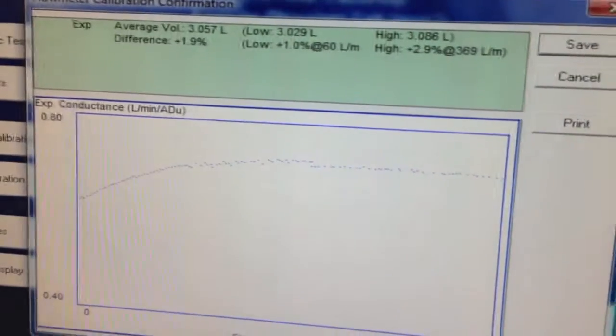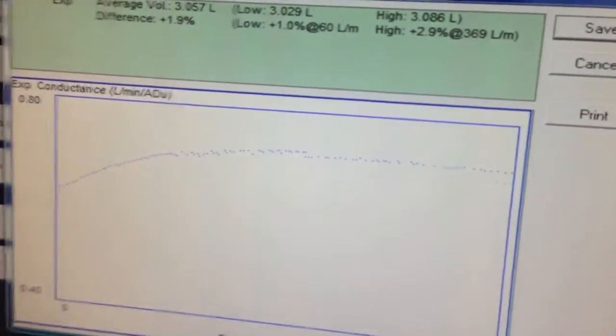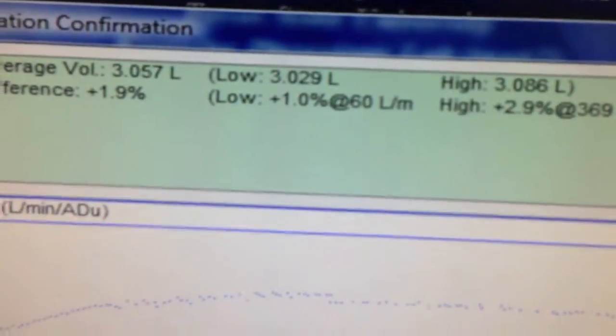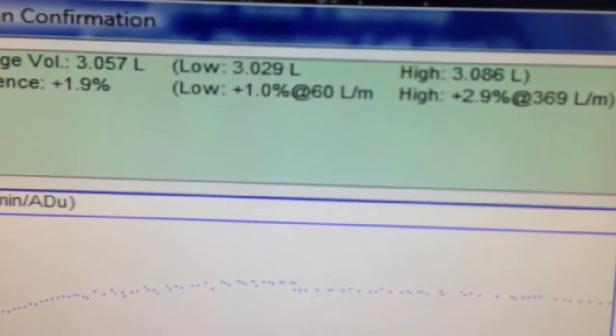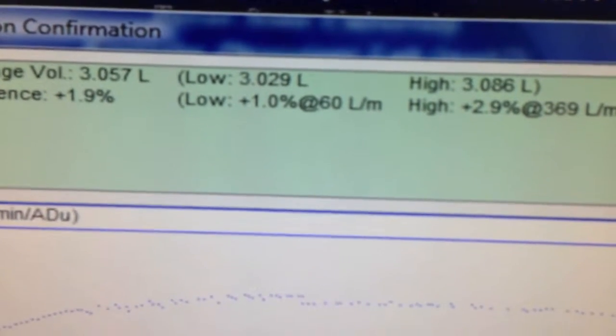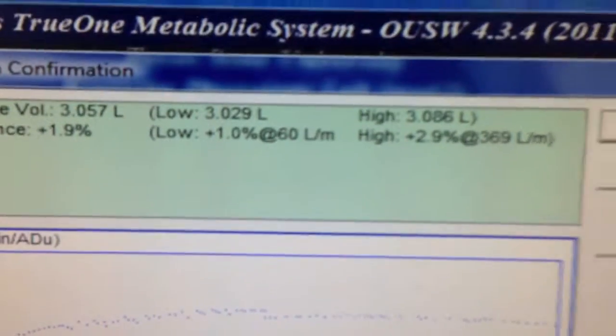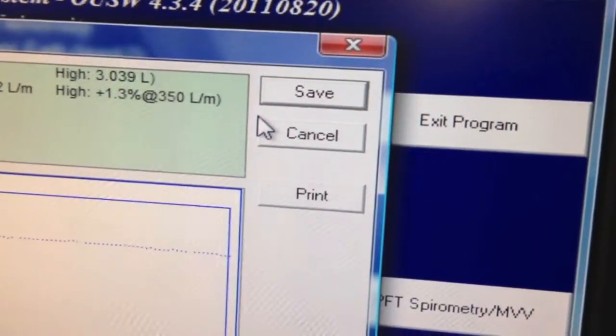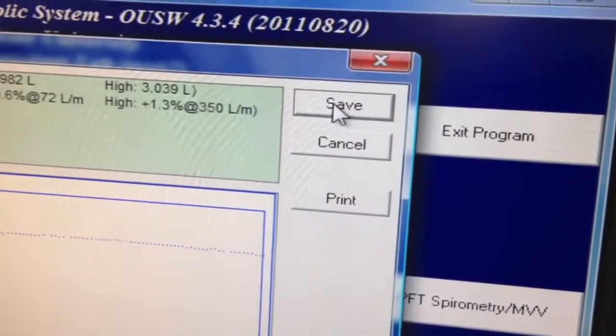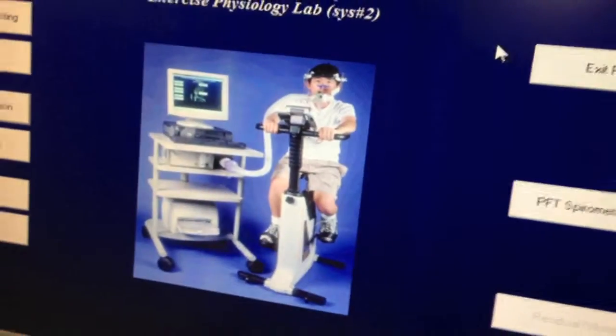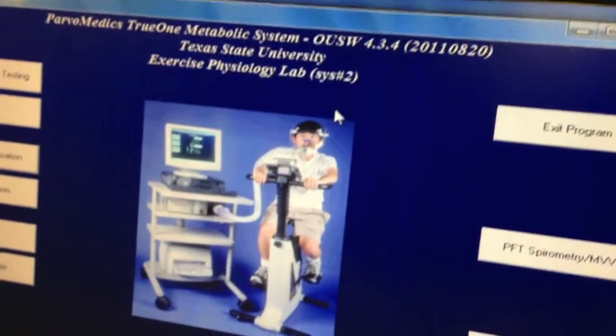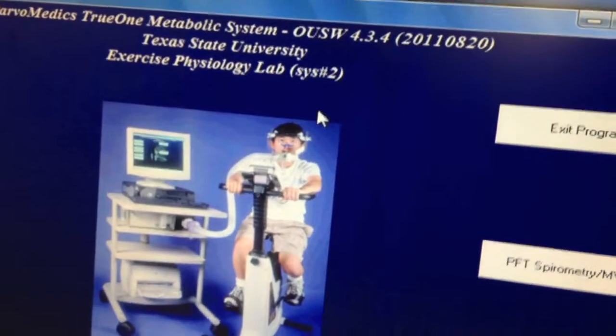Once flow meter calibration is complete, you'll want to look at the low to high difference. If the difference between these 2 values is greater than 5%, the calibration must be redone for accurate testing. After checking the values, you want to hit save, and you will end flow meter calibration. You will then be ready to test VO2 max and metabolic testing.